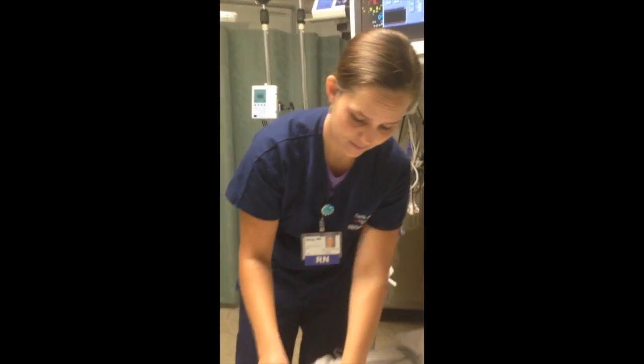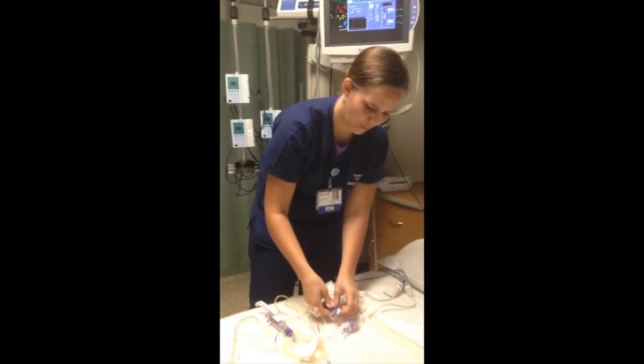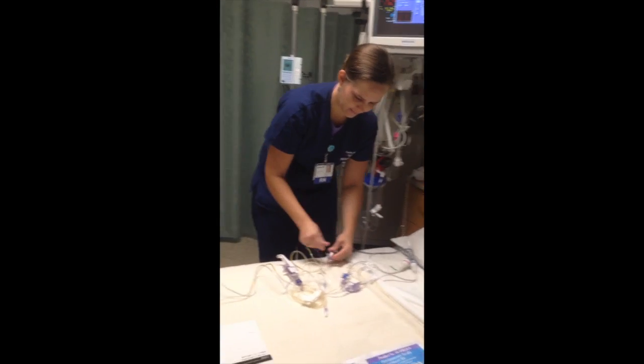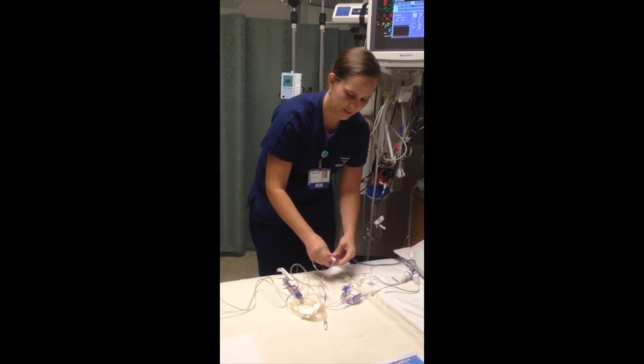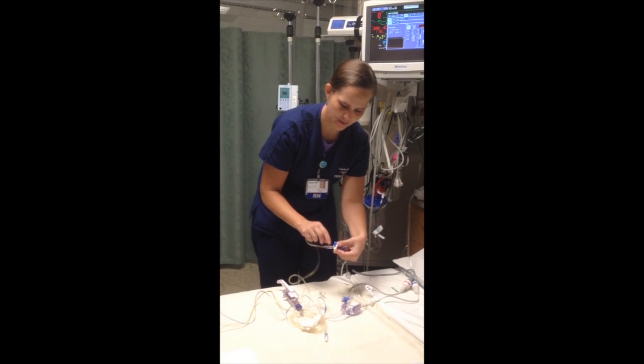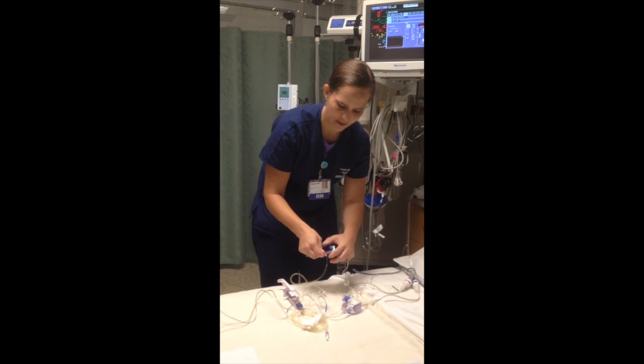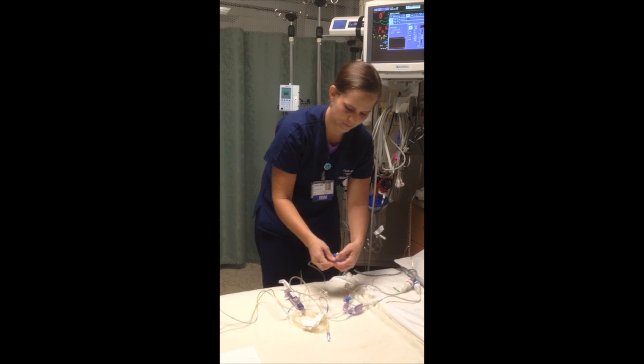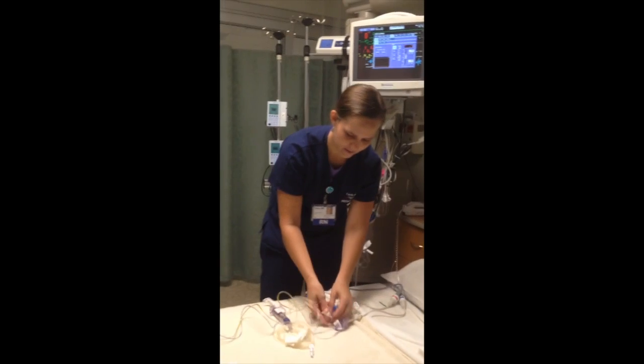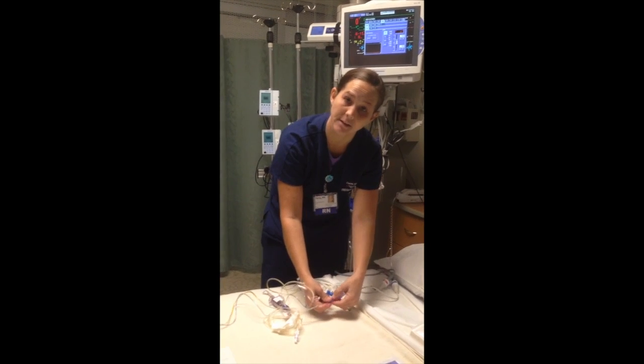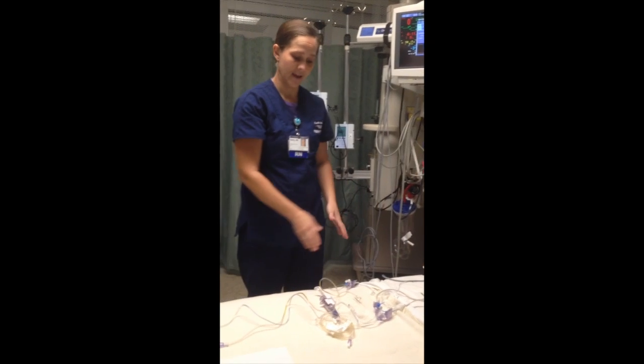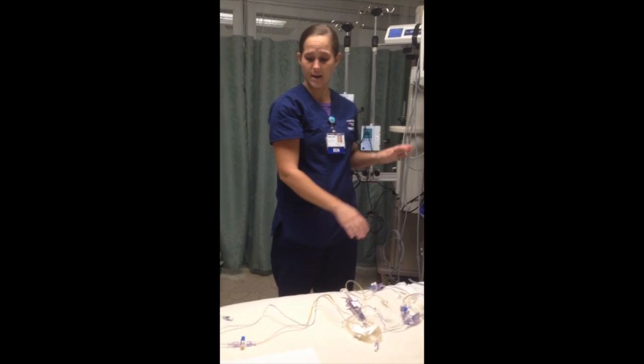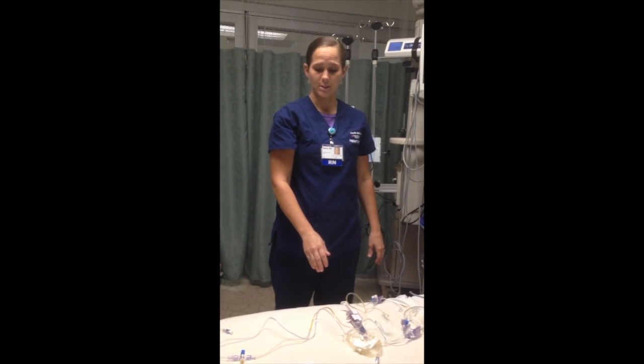One more thing I meant to say while priming your tubing is that I like to check these connections here. Sometimes they're loose, like this one, and it'll pop off at times, which can lead you astray. So just make sure you check all your connections and they're tight. And again, we like to have it zeroed, primed, set up, ready to go when the physician comes in.